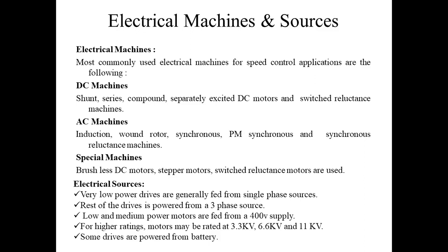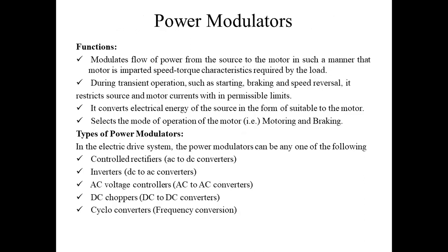So we have an electrical source. I already told you, very low power devices are generally fed from single phase sources. If we need a high power drive, we can get it from a three phase supply. For higher ratings, motors are rated at 3.3 kV, 6.6 kV and 11 kV. Some drives are operated from a battery also.